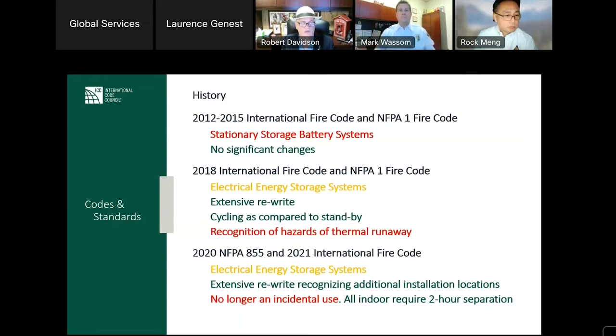As soon as the work got done on those two fire codes, NFPA had created the NFPA 855 energy storage system standard. Many of the people who worked on the two fire codes joined additional people from industry on NFPA 855. Looking at what was already in the fire codes, NFPA 855 was extensively rewritten and expanded, particularly because of the input of industry, giving us other areas where they would most likely be installed, other hazards we had to address, places we could lower some protection levels.